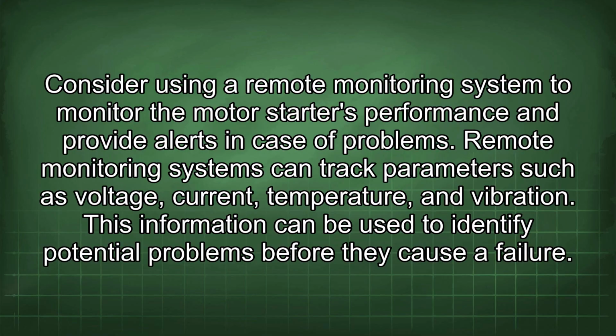Consider using a remote monitoring system to monitor the motor starter's performance and provide alerts in case of problems. Remote monitoring systems can track parameters such as voltage, current, temperature, and vibration. This information can be used to identify potential problems before they cause a failure.